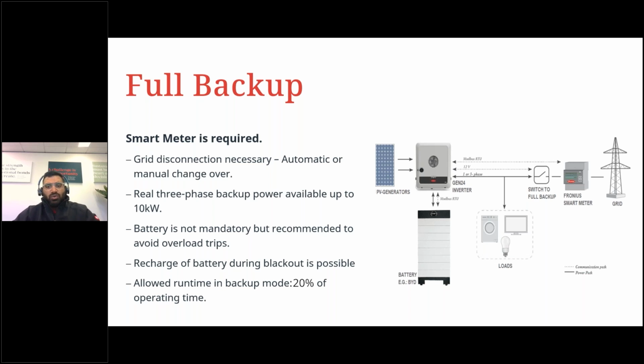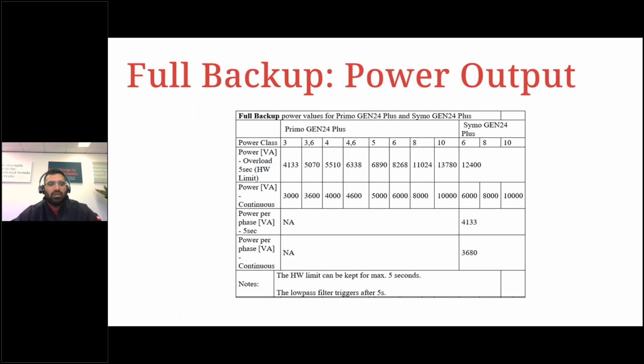With regard to the SYMO inverters, in full backup we are able to do a real 3-phase backup up to 10 kilowatts. And with a GEN24, you can also charge the battery while we are running the system in backup using the Multiflow technology. But please note that GEN24 Plus is a grid-connected inverter with emergency backup. We'll be looking more in detail at how to set up automatic changeover for full backup in the upcoming slides. Before that, let's take a look at what is really possible with the full backup and what output powers we can do.